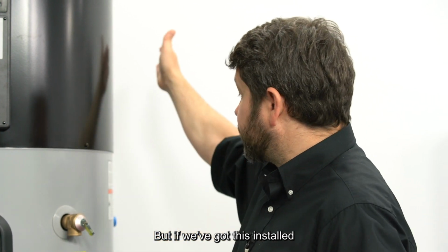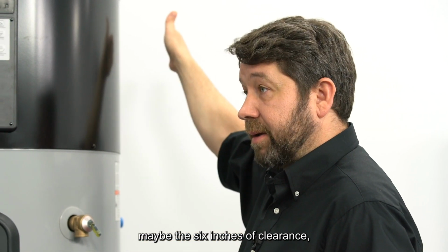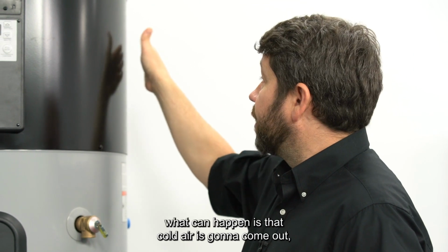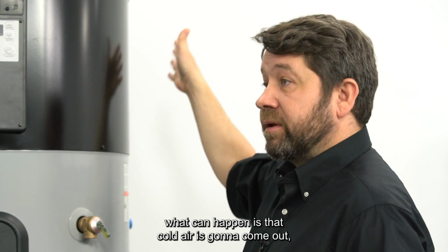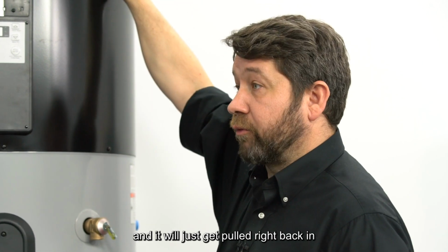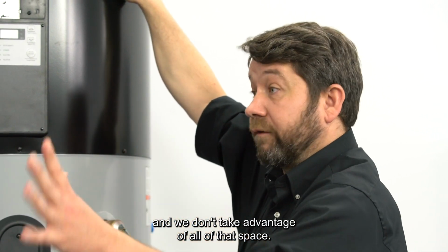But if we've got this installed where there's a wall right here, maybe the 6 inches of clearance, what can happen is that cold air is going to come out, it'll hit that obstruction, and it'll just get pulled right back in, and we don't take advantage of all of that space.